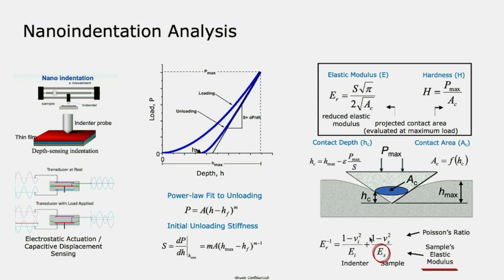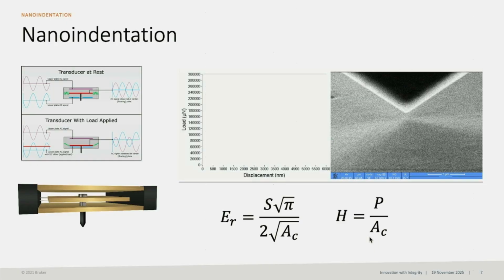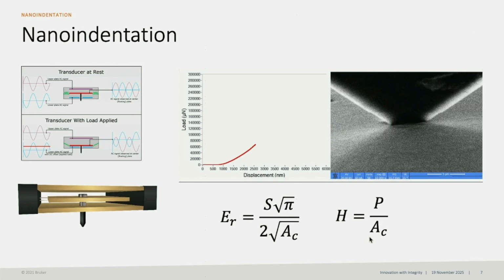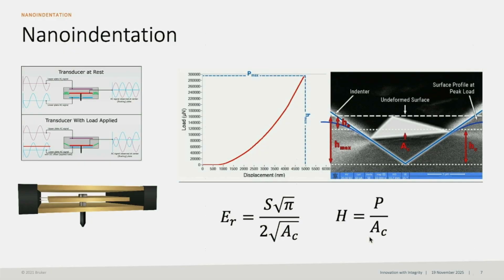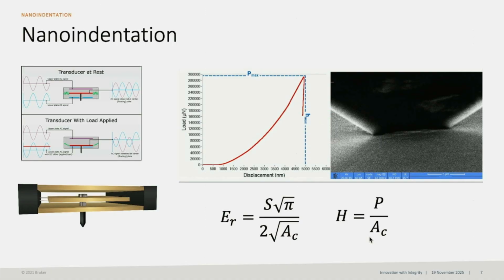And why is this in the nanoscale? Because the transducer must be very accurate. The displacement is accurate to below-nanometer accuracy. Also, the force has very high resolution, about nano-Newton resolution. So everything we are looking at here is on the nano and micro scale. And this is the video we are showing of nanoindentation inside of the SEM. So this is the probe, just what I said. We indent into the material and calculate the contact area, then we get the elastic modulus and hardness.